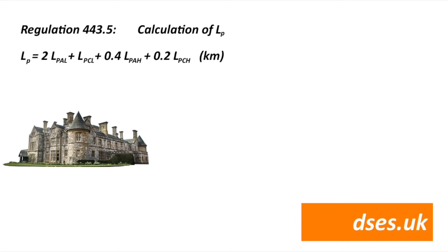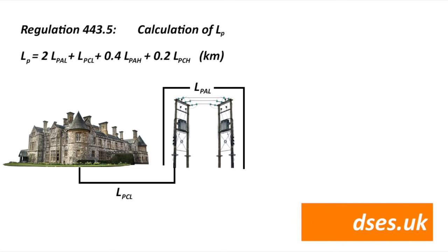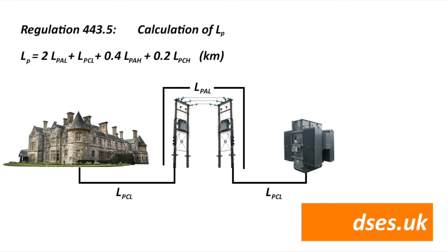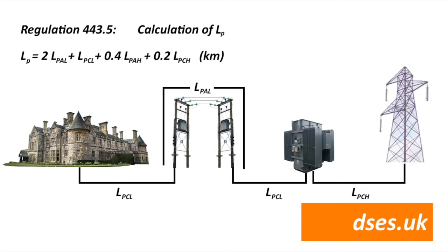So let's start with LPCL, as that's the bit that's connected to my house. Indeed, it's the length of the low voltage underground cable between my intake position and the nearest LV transformer, illustrated here as being pole mounted. Although that may not be the case, of course. Now we have LPAL, which is the length of the low voltage overhead line. Then we have some more to factor into LPCL, where the cable runs between the high and low voltage transformers. LPCH is the length of high voltage underground cable, and LPAH is the length of high voltage overhead line. Now, different installations will be fed in differing ways.